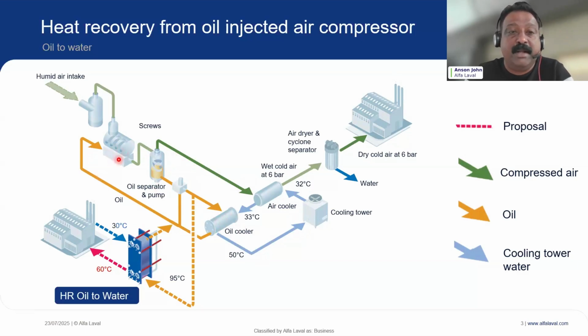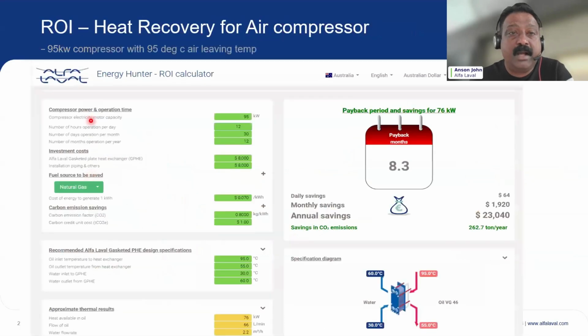That's pretty normal. And what we are suggesting to the market is to add a plate type heat exchanger to do heat recovery from this hot oil, which is at 95 degrees C. So you can have piping to the inlet of a plate type heat exchanger at 95 degrees C, and then you can heat up the water from 30 degrees to 60 degrees or even higher, which can be used in different applications. That also will reduce the size of your oil cooler and the size of the cooling tower. So those are additional advantages. And Alfa Laval has a pretty good return on investment calculator, which is pretty smart.